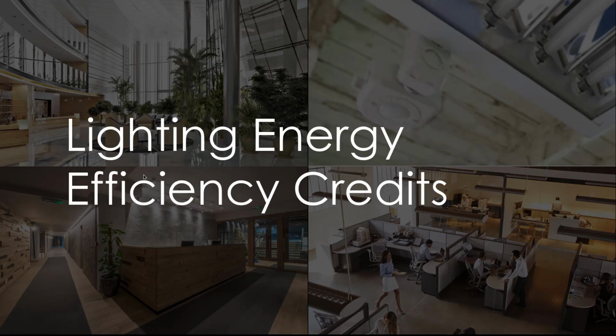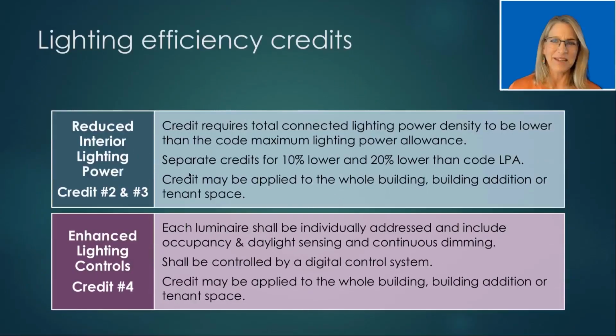Now let's talk about lighting systems. There are 2 lighting efficiency credit package types: reduced interior lighting and enhanced lighting controls. To comply with a reduced interior lighting power credit, the total connected lighting power density must be lower than the code maximum lighting power allowance. There are separate credits for 10% lower and 20% lower than the code LPA, and this credit may be applied to the whole building, building addition, or the tenant space.